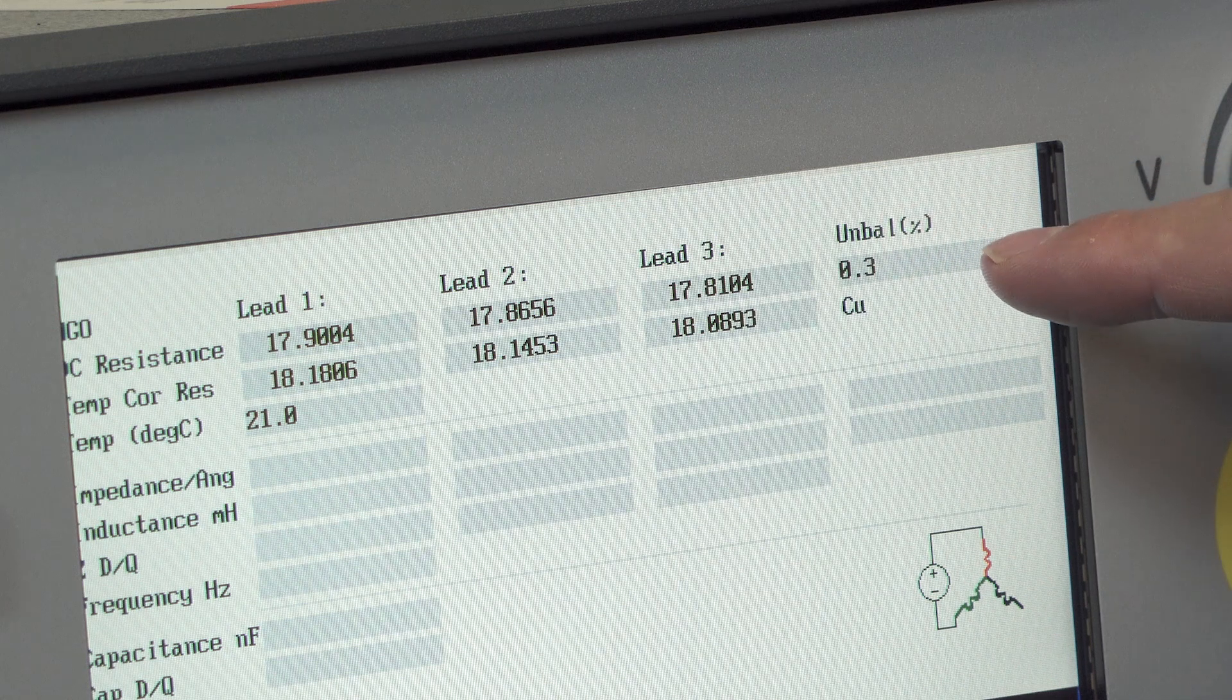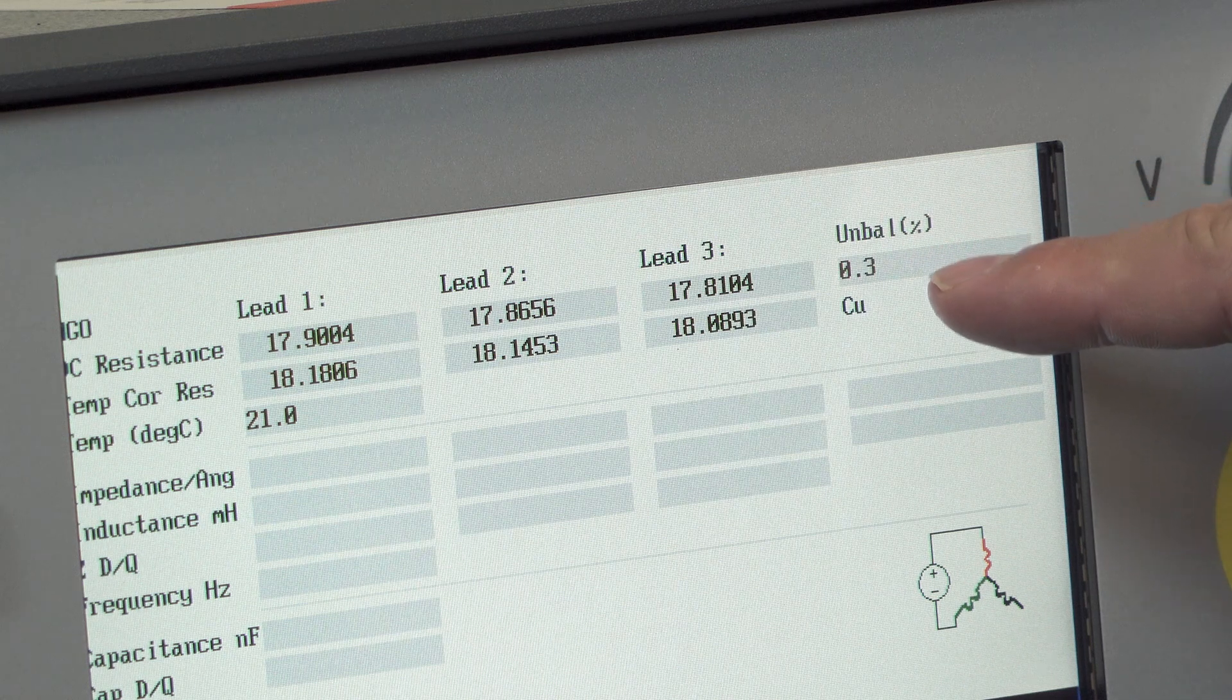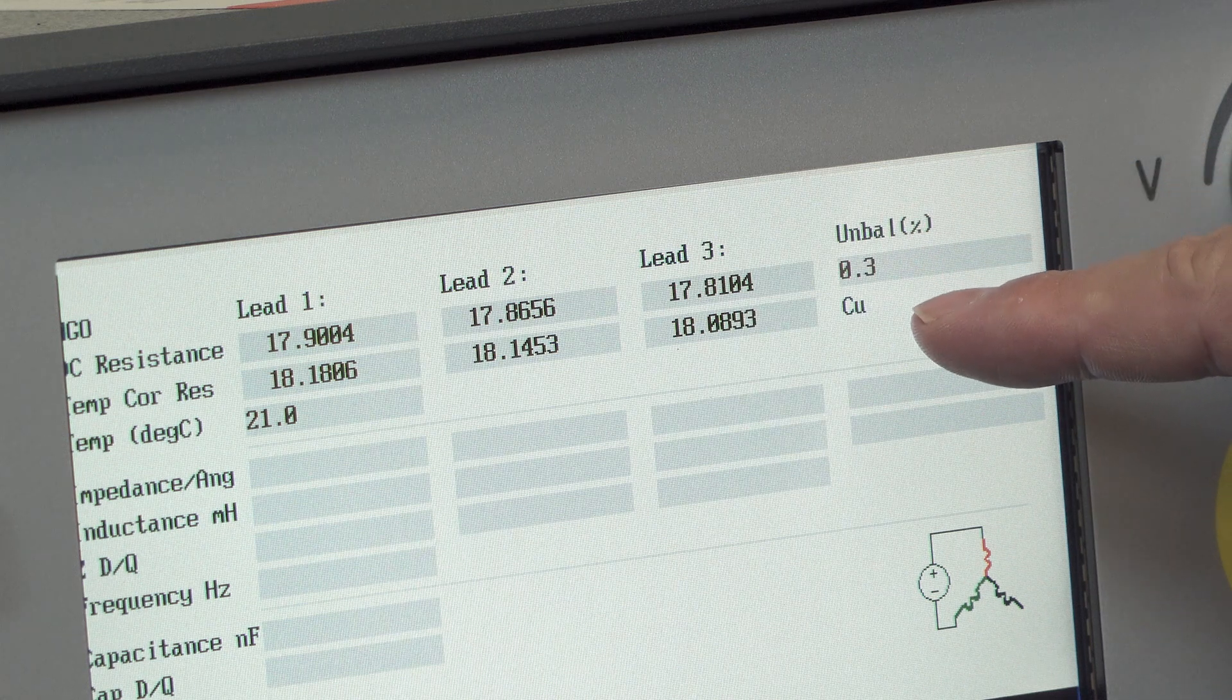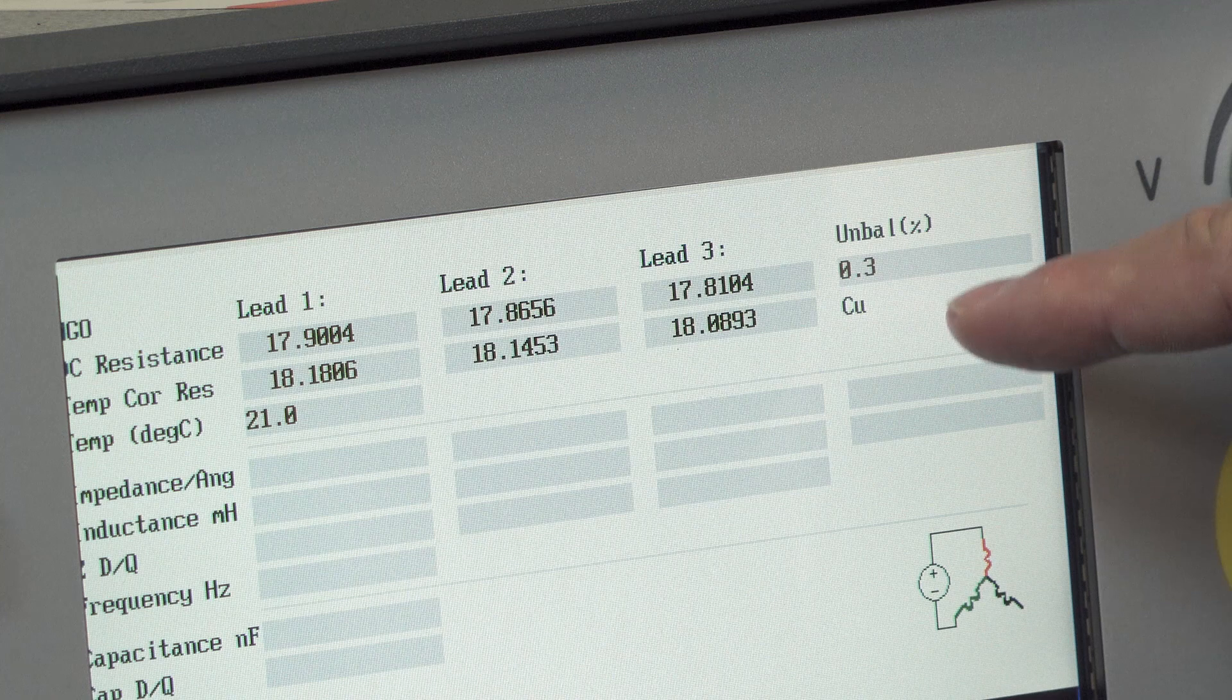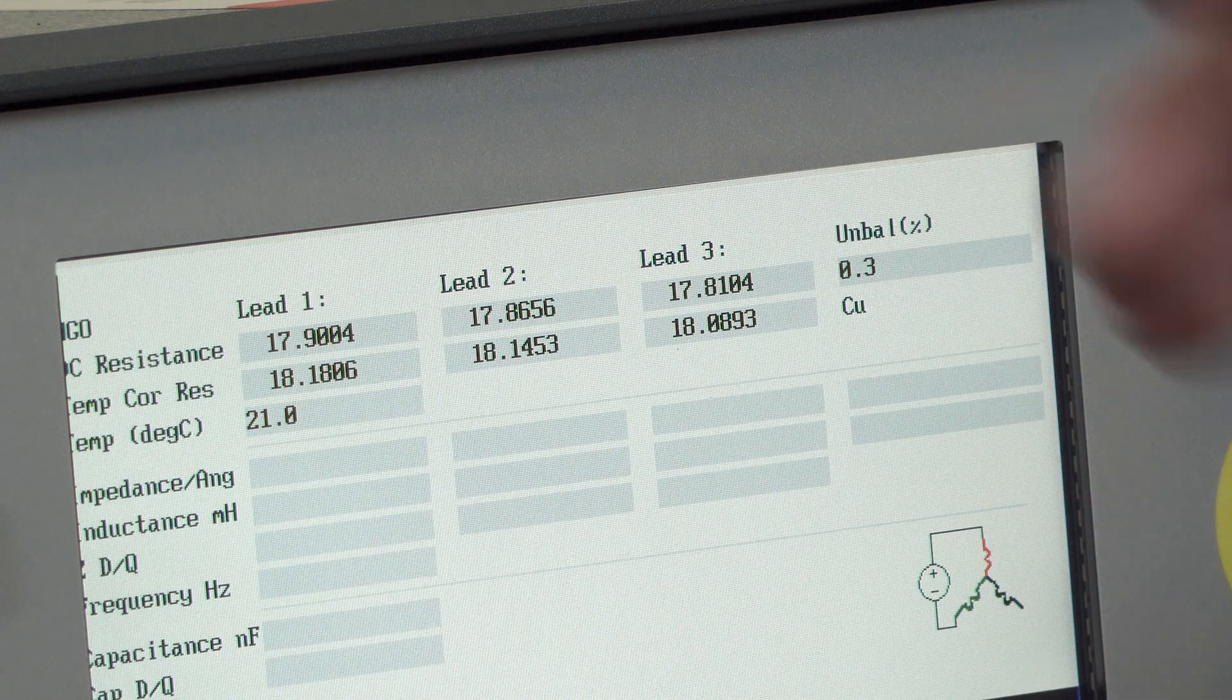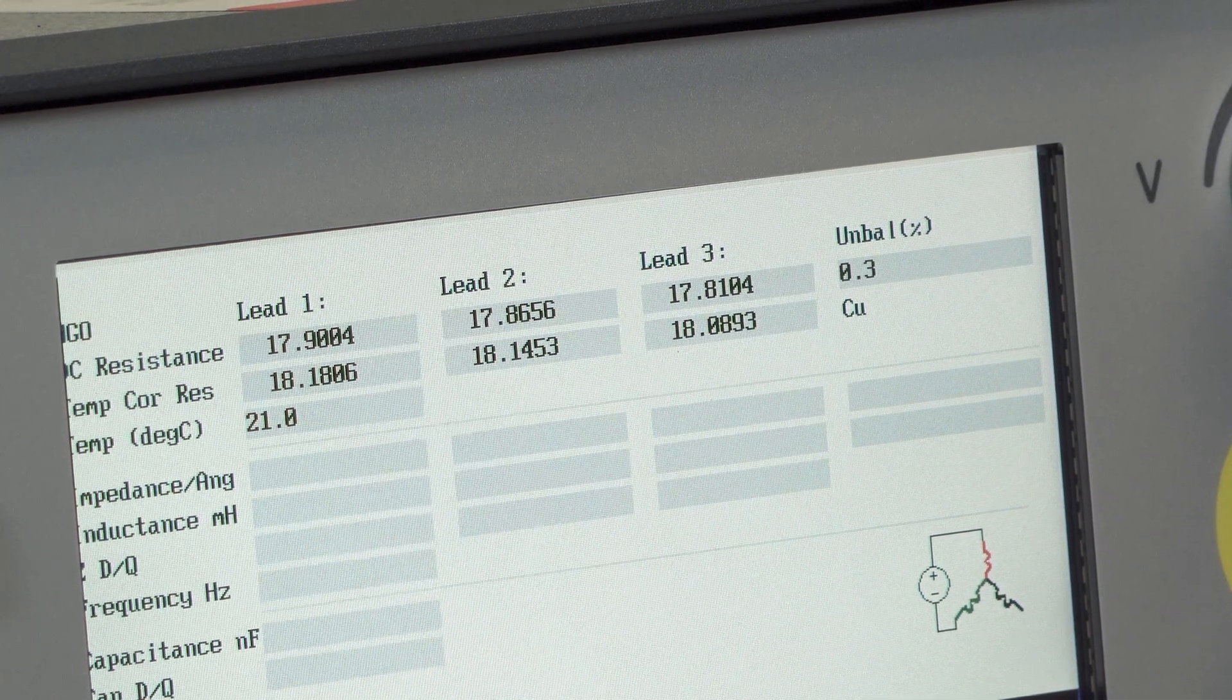And then from the last column we have the calculated imbalance, resistive imbalance. In this case 0.3% showing that the resistance is very balanced in the circuit.